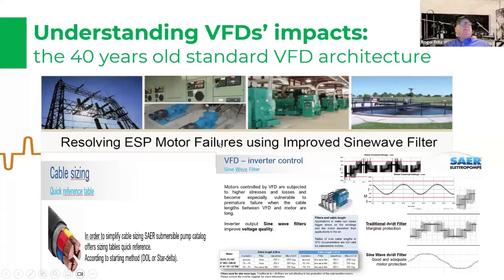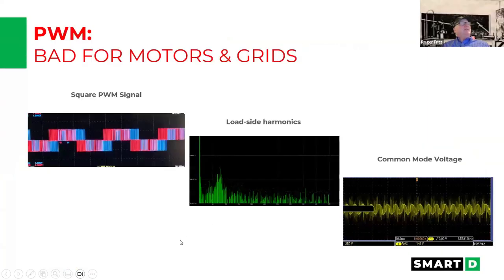Like these are deep well submersible oil pumps, and they're actually massively requiring what they call these VFD pure sine wave filters. So they put this on the output side of the drive, and it does clean it up, but there still is quite a bit of dV/dt down here in the jags that is not able to be overcome. And then on the primary side, because of long lead lengths, they're putting in specialized shielded cable because that choppy input power is distorting the power source. So this gives you an idea of the PWM output signal. This is the harmonic side of the output.